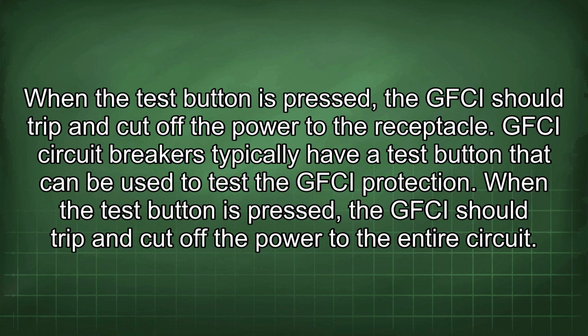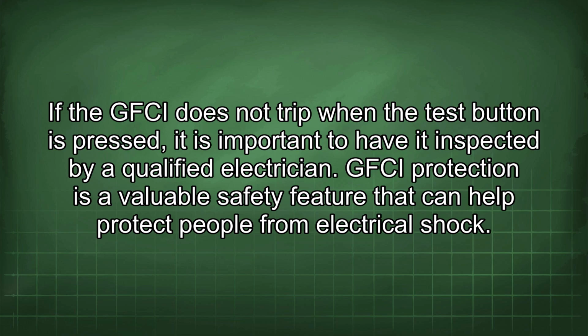GFCI circuit breakers typically have a test button that can be used to test the GFCI protection. When the test button is pressed, the GFCI should trip and cut off the power to the entire circuit. If the GFCI does not trip when the test button is pressed, it is important to have it inspected by a qualified electrician. GFCI protection is a valuable safety feature that can help protect people from electrical shock.